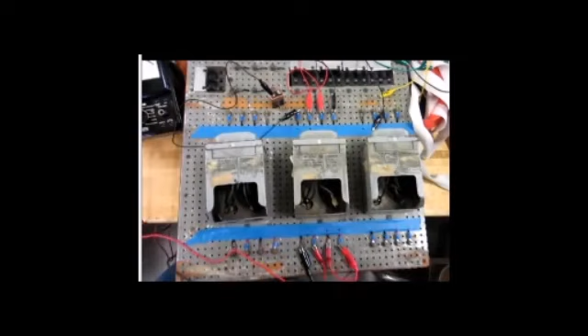Hi, this is Minhee again, and I'm going to show you the kick test on a board. This is my battery, a DC battery, connected to the positive polarity. These are two jumpers connecting the winding - the primary has one jumper and the secondary has one jumper, connecting the polarities and putting the coils in series. Both primary and secondary have that.